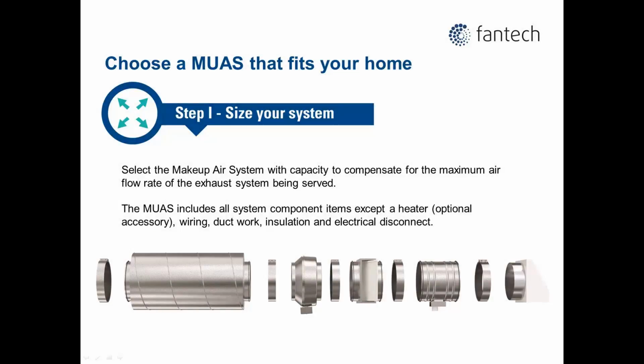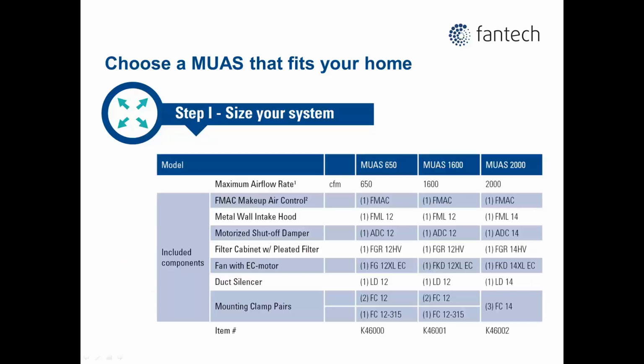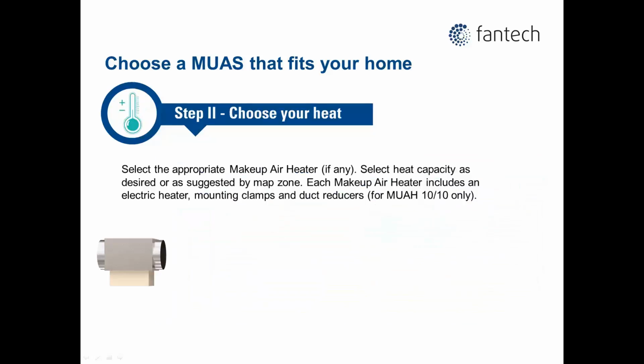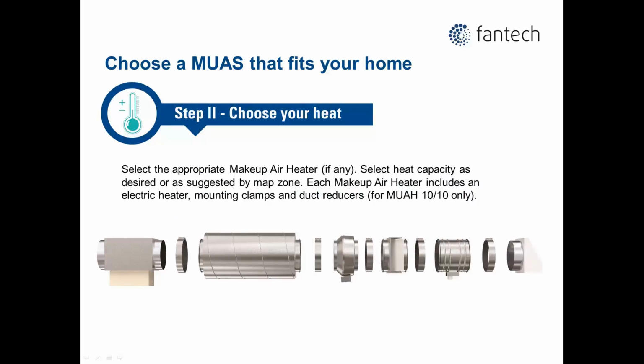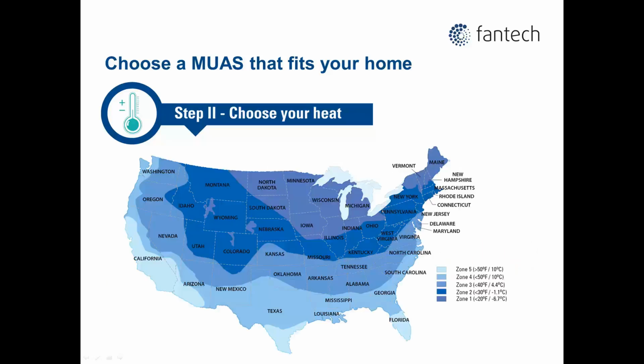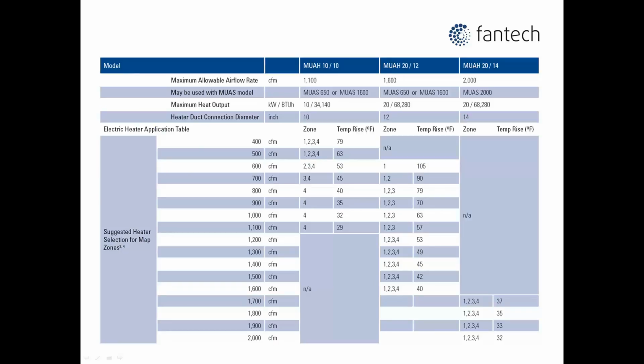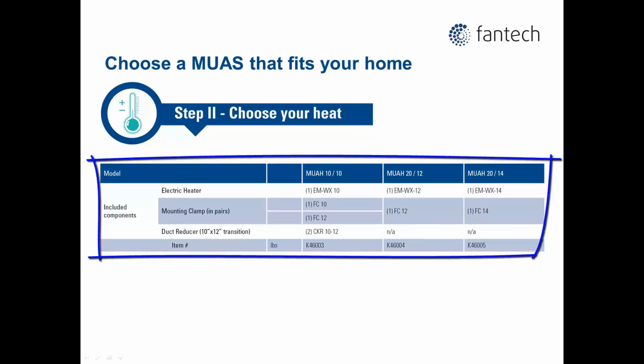Selecting your Fantech make-up air system is a very simple two-step process. These three easy-to-size systems with airflows up to 2000 CFM at 0.5 will cover the vast majority of residential range hood exhaust systems. To go along with this, there are three heater combinations for various airflows and delivered air temperatures. If unsure of your requirement, from the map, select the heater based on your geographical location and the average outdoor temperature. Then simply select the heater based on the exhaust fan's maximum airflow, the temperature zone you're in, and the temperature rise required. The selected heater comes with all components to fit into your Fantech make-up air system.